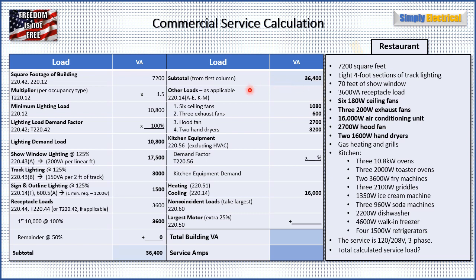Next we go on to other loads — pretty much anything we haven't considered yet, aside from kitchen equipment and heating and cooling. We have 6 ceiling fans at 180 watts each: 6 times 180 is 1,080 watts. We have 3 exhaust fans at 200 watts each: 600 watts total. We have a 16,000-watt AC unit, which we'll list separately down below to compare against heating later. We have a 2,700-watt hood fan — which does not go under kitchen equipment, as I'll explain. And we have two 1,600-watt hand dryers: 3,200 watts total.